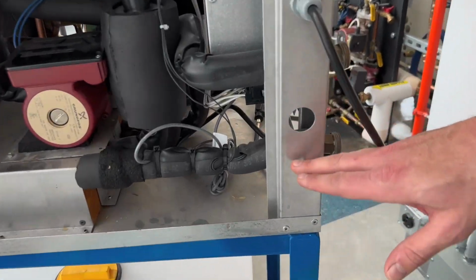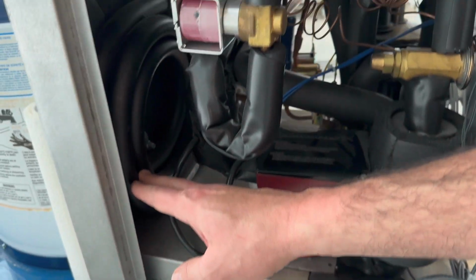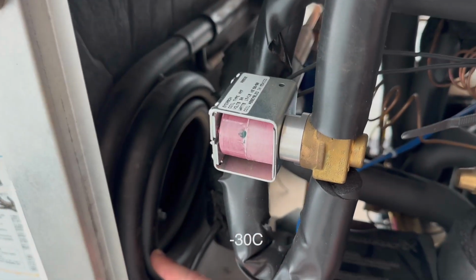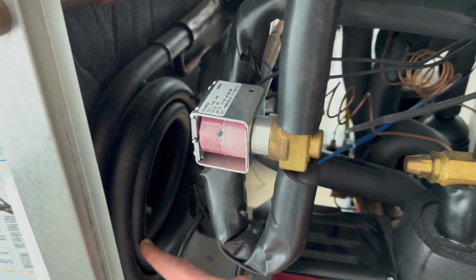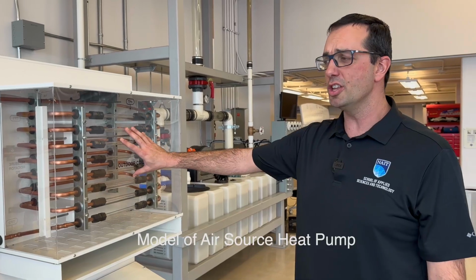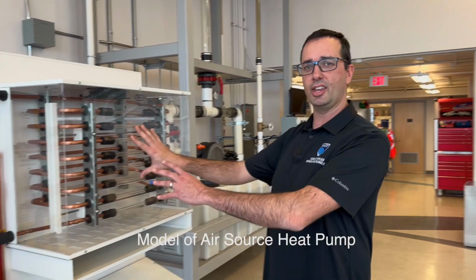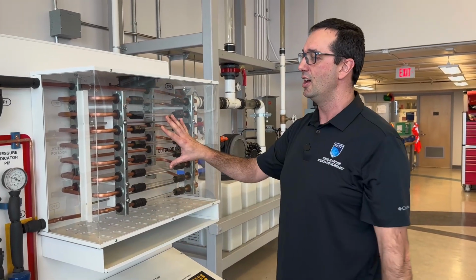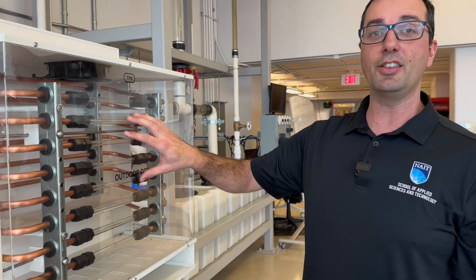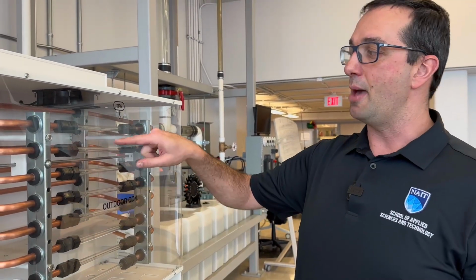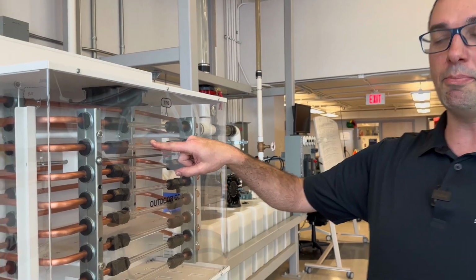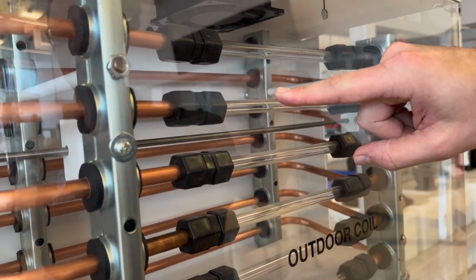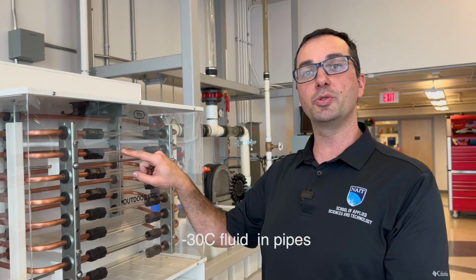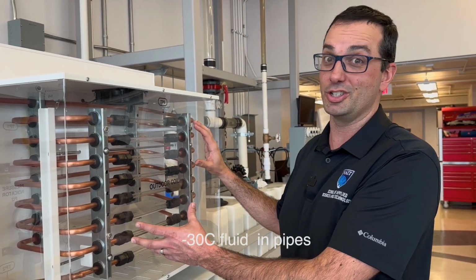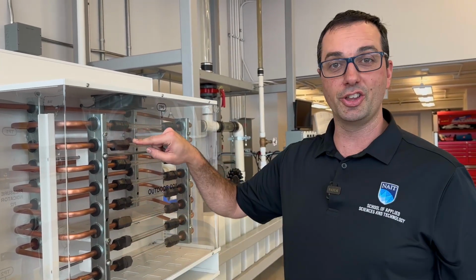So the heat pump actually chills the fluid to minus 30 before sending it to the minus 10 degree air outside. Let's start from the outdoor unit. We want to bring heat from the outside to the inside, so we need to take heat from minus 10 Celsius and put it inside these coils. The heat pump holds these coils at a temperature of around minus 30 degrees Celsius, so heat naturally goes from the minus 10, which is relatively hot, to the minus 30 inside the coils.